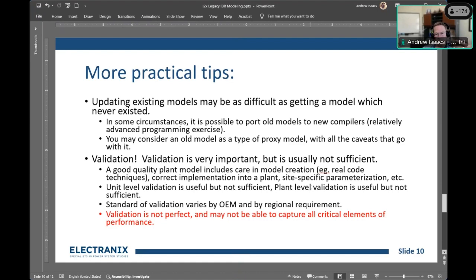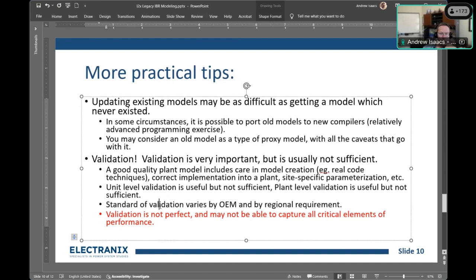And plant level validation is also insufficient because it's very difficult to get conditions correct enough in your models to represent the system condition where the event occurred, and the event is not comprehensive either. It's a single fault, maybe, that goes to a certain voltage depth and a certain system strength. So we don't have a way to thoroughly test the model at the plant level either. And as Miguel said, the standard of validation also varies by OEM and by regional requirements, so there's no good agreement on how good the validation has to be.